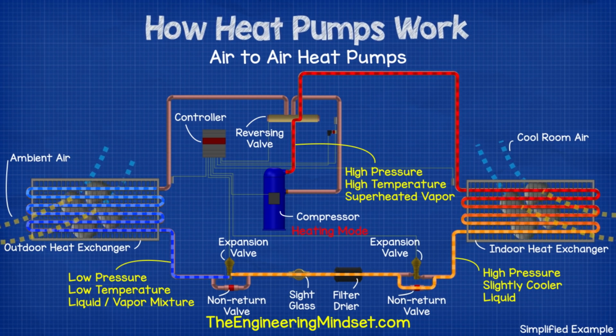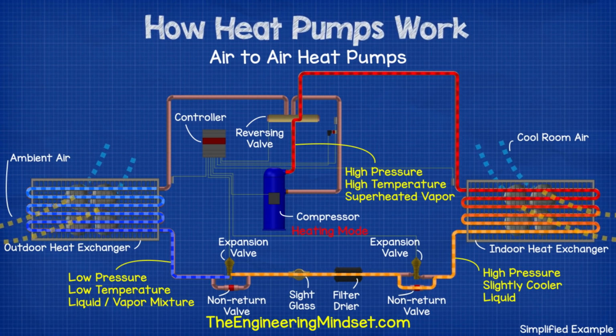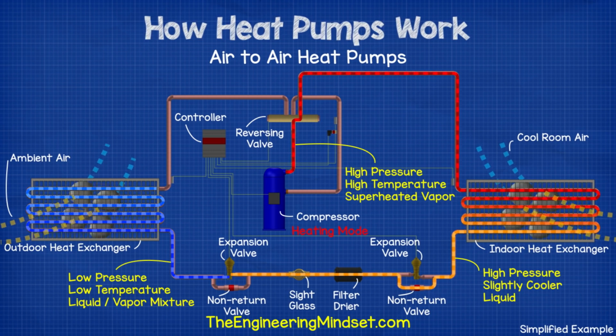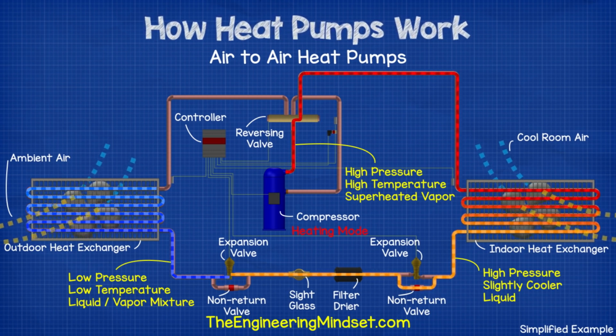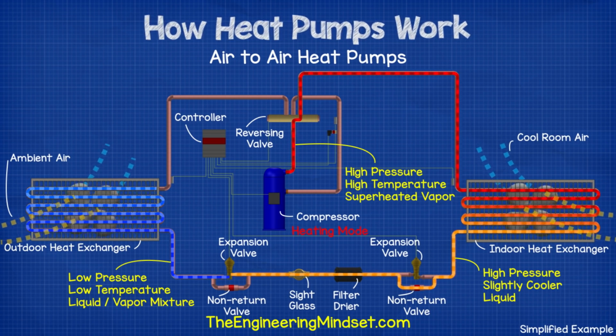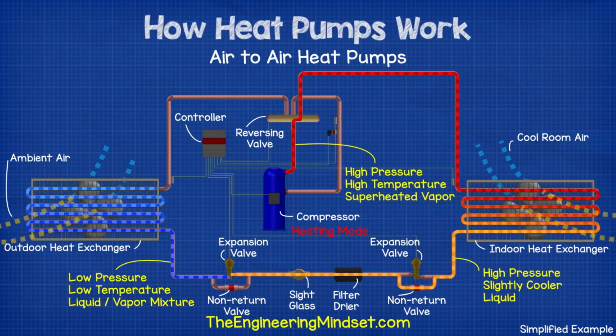The refrigerant then heads to the outdoor heat exchanger. Here, a fan is blowing outside ambient air over the coil and adding heat to the cold refrigerant. The refrigerant boils at a very low temperature, and as it boils, it will carry away the thermal energy.